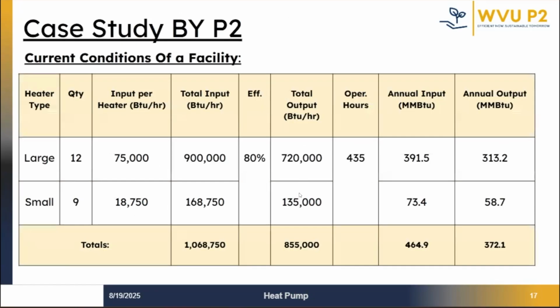So let's talk about one of the facilities where an energy assessment was done by our P2 group, at a warehouse. The warehouse was equipped with 12 large and 9 smaller low intensity tubular infrared natural gas heaters with an efficiency of 80%. The total output heat was around 855,000 BTU per hour and the input was around 464.9 MMBTU.